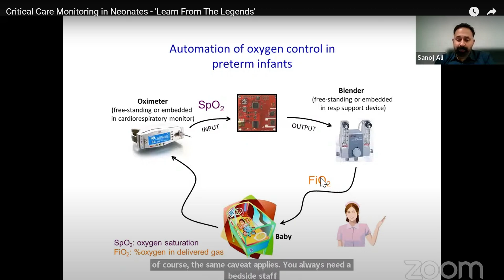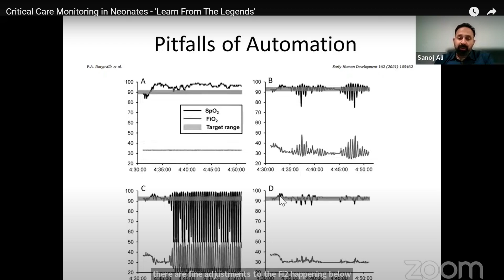This is if you don't adjust the FiO2, which is on the lower bar out here, the SpO2 in black fluctuates and doesn't stay within the target range. But if you have an algorithm which is overpowered, this is what results: you get this significant fluctuation, the FiO2 goes up and down, the SpO2 fluctuates accordingly, and that can be quite dangerous. And the last graph, graph D, is an adapted algorithm, so you can see that there are fine adjustments to the FiO2 happening below, and the SpO2 out here on the top stays within target range most of the time. This is what we'd ideally like to see.